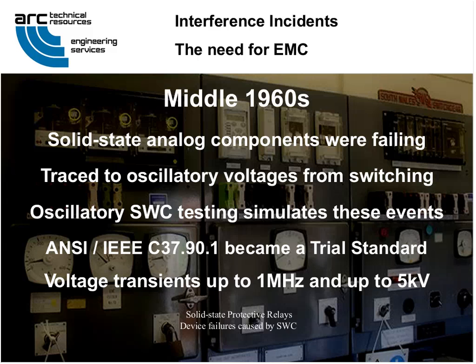The test simulates the oscillatory voltage transients up to a megahertz and 5 kV on the control wiring resulting from these switching operations. All the major relay manufacturers needed to retest their designs to make sure they exhibited immunity to these simulations without false operations, or frankly, utilities wouldn't buy their stuff.